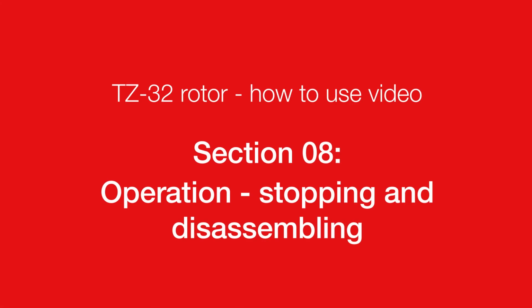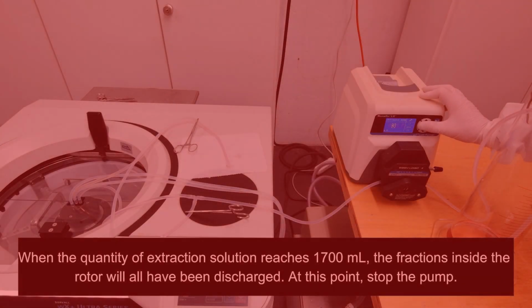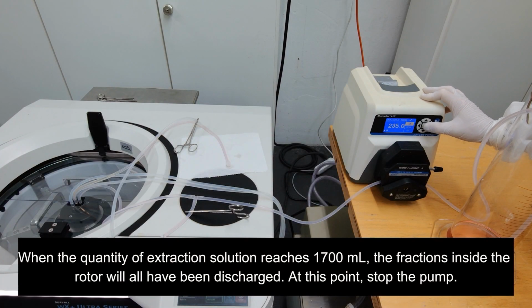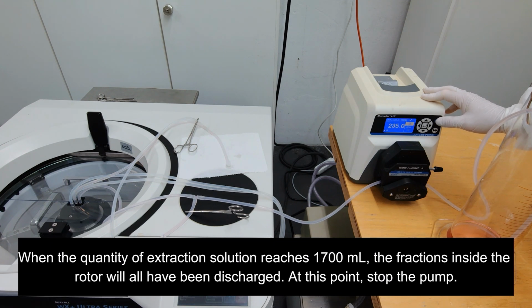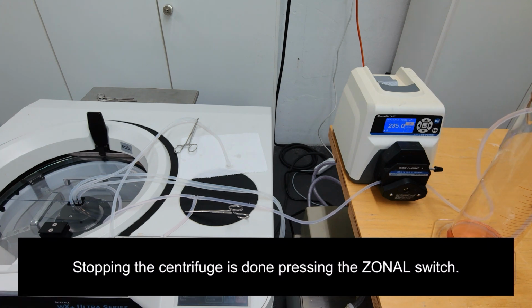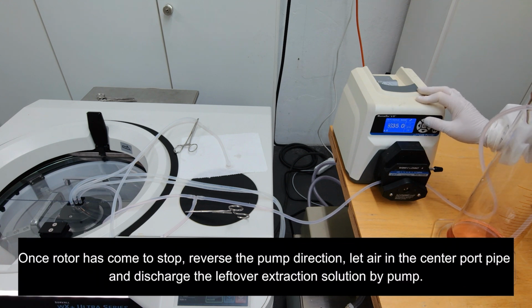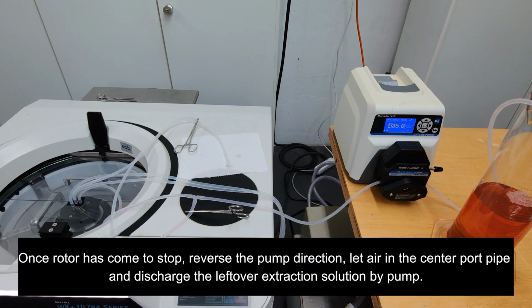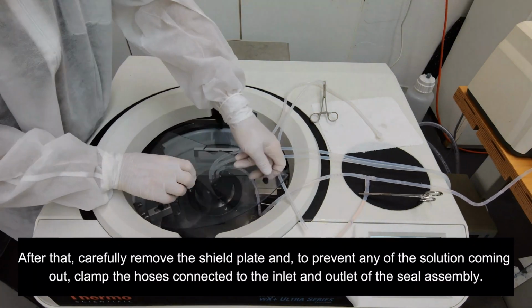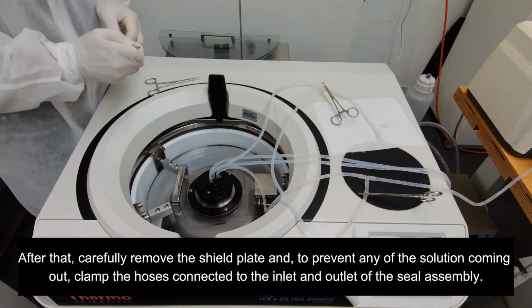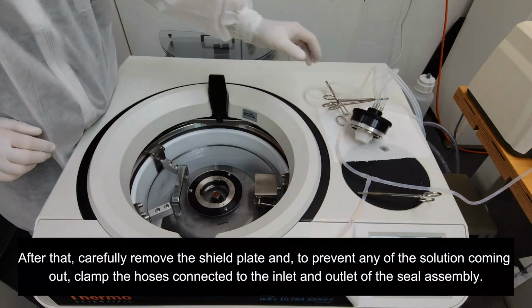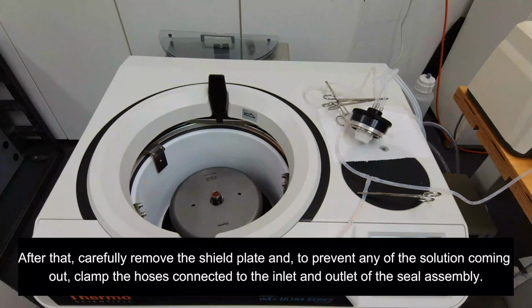How to use video. Section 8. Operation, stopping and disassembling. When the quantity of extraction solution reaches 1700 ml, the fractions inside the rotor will all have been discharged. At this point, stop the pump. Stopping the centrifuge is done by pressing the zonal switch. Once the rotor has come to a stop, reverse the pump direction, let air in the center port pipe and discharge leftover extraction solution by pump. After that, carefully remove the shield plate and, to prevent any of the solution coming out, clamp the hose connected to the inlet and outlet of the seal assembly.